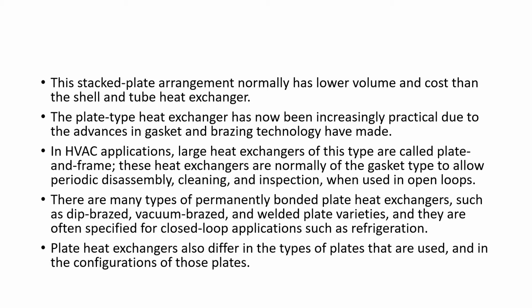So in HVAC applications, large heat exchangers of this type are called plate and frame. These heat exchangers are normally of the gasket type to allow periodic disassembly, cleaning, and inspection when used in open loops. There are many types of permanently bonded plate heat exchangers, such as dip-brazed, vacuum braze, and welded plate varieties, and they are often specified for closed loop applications such as refrigeration. The plate heat exchangers also differ in the type of plates that are used and in the configuration of those plates.